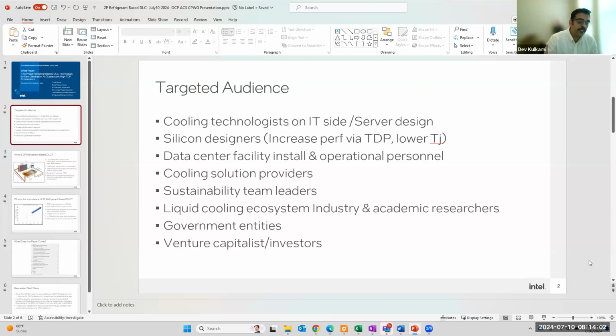Use the same server design and choose whichever cooling technology you want to use, whether it's single phase, two phase, low pressure, medium pressure refrigerant, et cetera. Again, this particular technology brings sustainability KPIs like lower PUE and TCO, because you can use quite warmer refrigerants to cool kilowatt-plus accelerators. That can eliminate or reduce the need for chillers, which are basically the energy hog, and bring the PUE down. So for the folks who care about sustainability, this may be a good technology to look into.